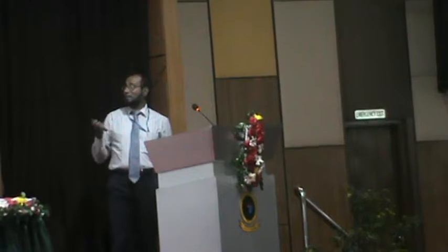And then this is the relation. What equipment is needed? Healthcare regulatory, Director General Health Service, Healthcare Engineering Department, Clinical and Biomedical Engineering Department need preventive maintenance, calibration, clinical setting, because, like a computer, as my keynote speaker previously told, equipment needs calibration and data, because a machine has some default settings.